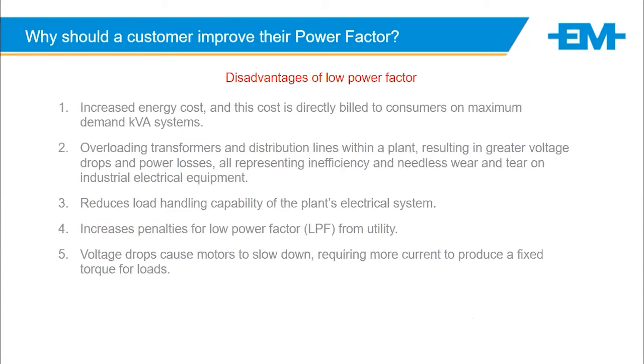So why should a customer improve their power factor? Firstly, increased energy cost, and this is a direct charge on your bill. So when you look at your utility bill, if you have a maximum demand, it is something you can address immediately. You cannot remove it completely. It will always be there, but you can reduce it and be more efficient. When you reduce your demand, you reduce the overloading on your transformers and the distribution line at the point of injection. Okay, so resulting in less voltage drops and power losses.